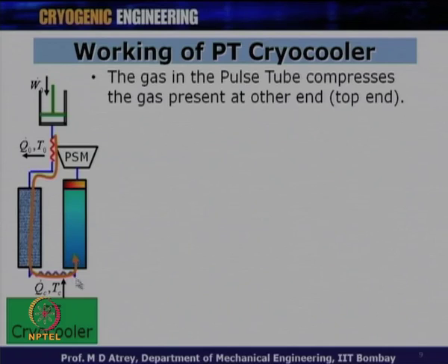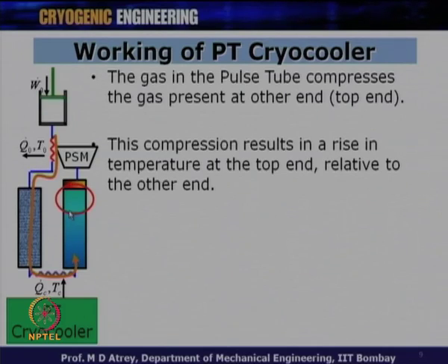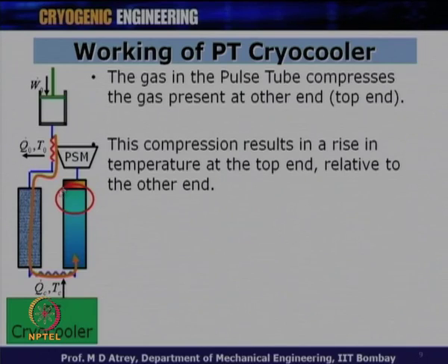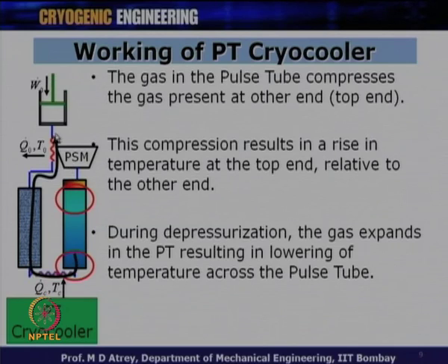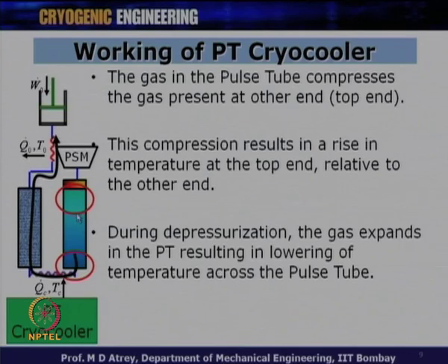Let us call this the top end and the other the bottom end of the pulse tube. The compression of gas already present by the incoming gas during pressurization results in a temperature rise at the top end — in fact, temperature rises at every point, but most at the top. During depressurization, the piston goes back and the gas in the pulse tube expands, resulting in lowering of temperature across the pulse tube.